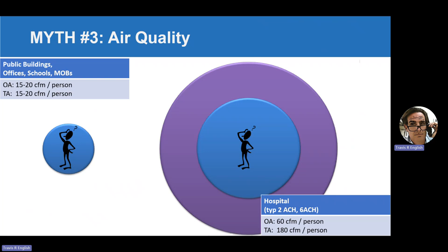I was fortunate enough to be a part of this. There was a California Energy Commission funded study at an active hospital that tested ventilation rates from 2 air changes up to 12 air changes. We had air quality sensors at 72 locations in the hospital using multivariable air quality sensors. And the data showed there's no air quality improvement from 2 air changes per hour to 12 air changes per hour. You know, the air quality is the same. Higher rates like 4 air changes or 6 air changes or 10 air changes provide no air quality benefit. You're basically just spending energy, or wasting energy, I should say.